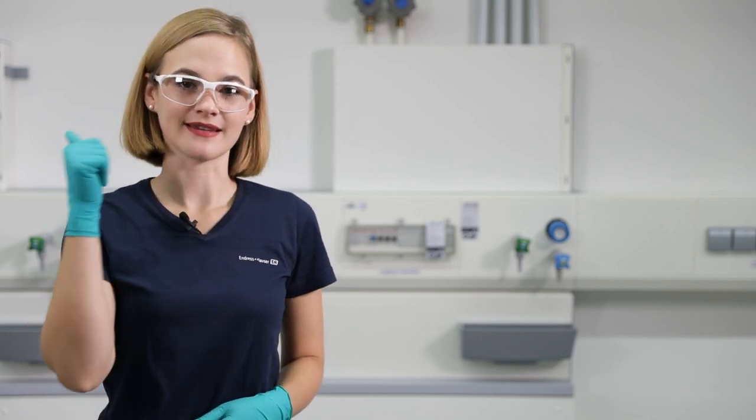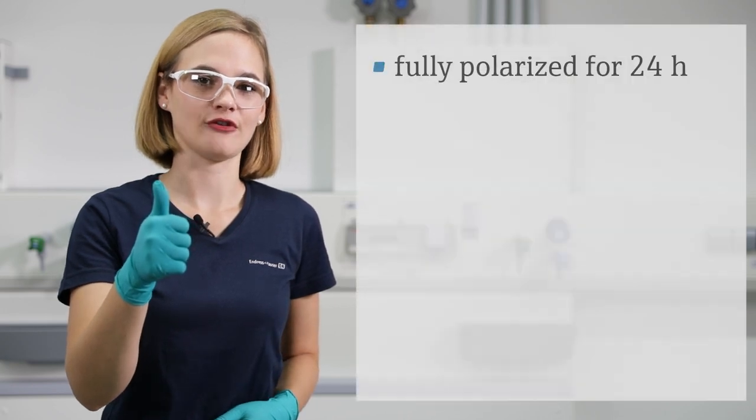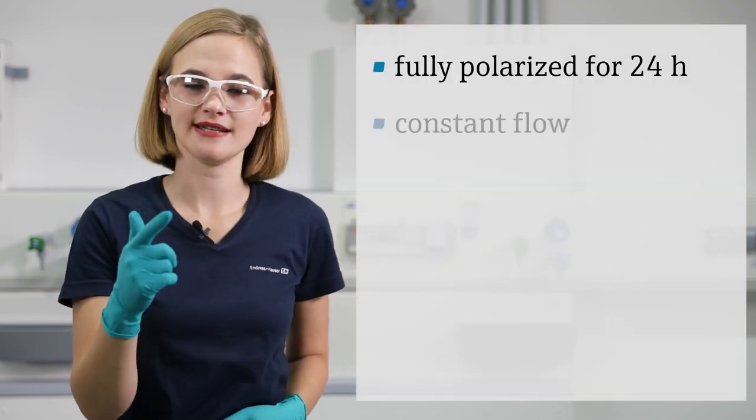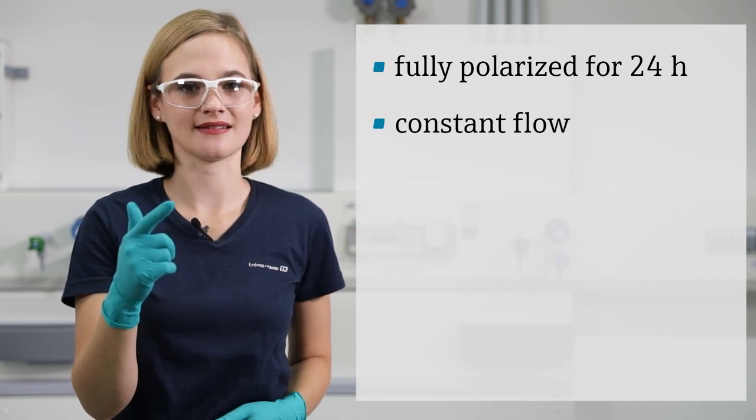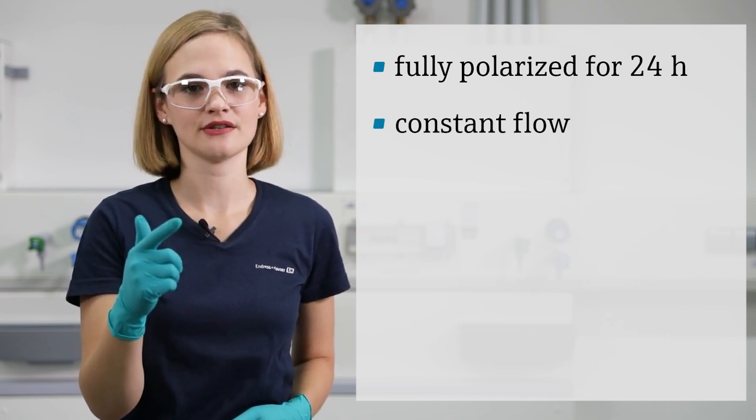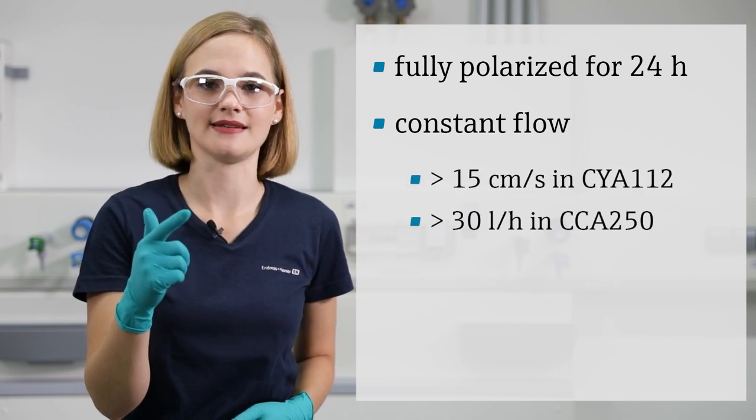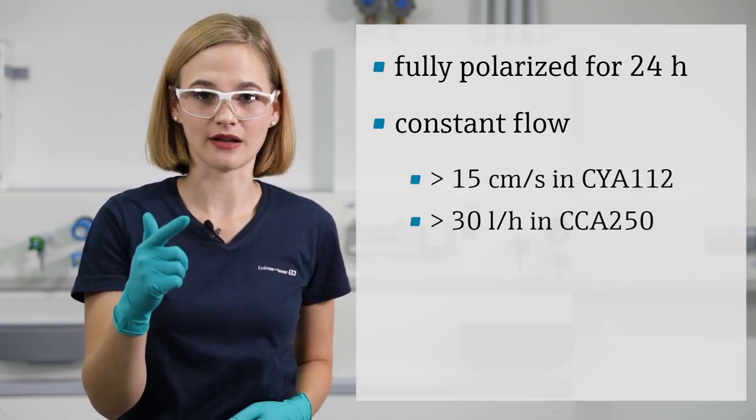The following preconditions support best results for calibration. The sensor is fully polarized for at least 24 hours. The flow velocity against the membrane is constant and within the correct range. This means more than 15 cm per second in the CYA112 assembly.